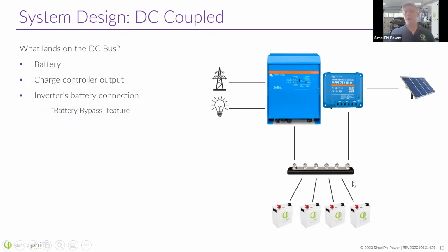So I remember when fancy new inverters were hitting the market when I was studying them in school, and they were coming out with this battery bypass feature. So they claimed they could take power from the PV array as it was coming in, and never have to charge the battery bank from it. Now, I think that's a little bit of a hoax feature because the DC bus bar does this automatically.